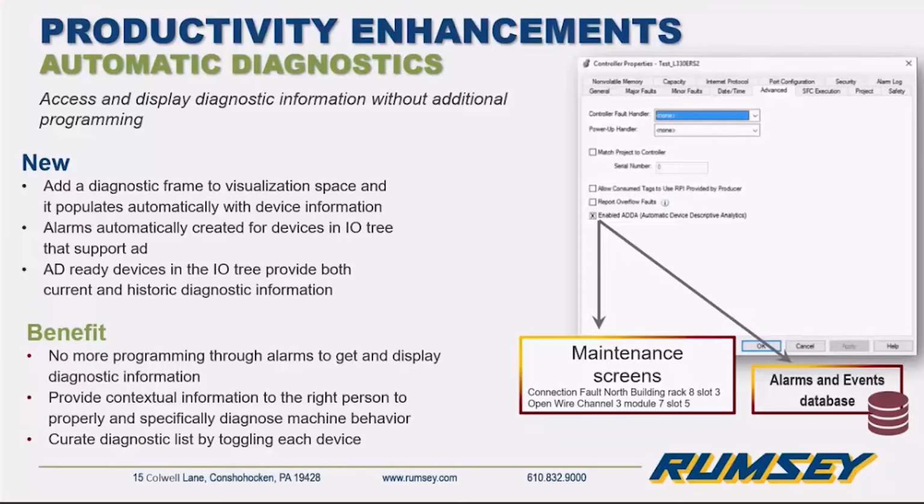That required programming, GSVs and doing some stuff for each item in the I/O tree. Usually took a while. Now you can just turn this on and it will automatically be generated for you. So this is a pretty big feature, big time saver. And it also kind of makes a consistent approach for it.